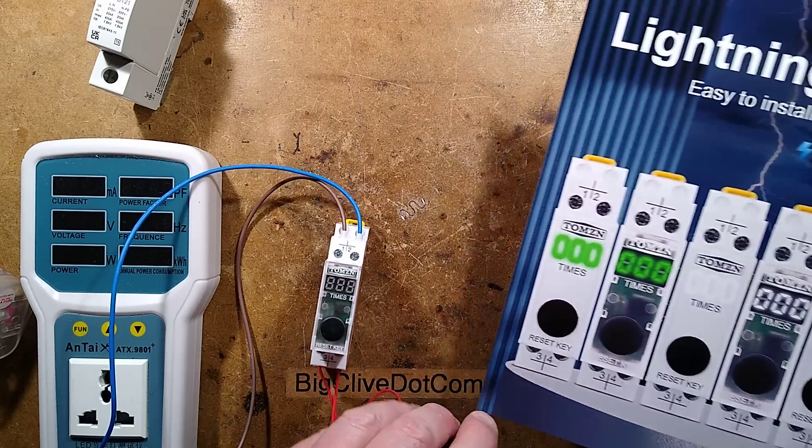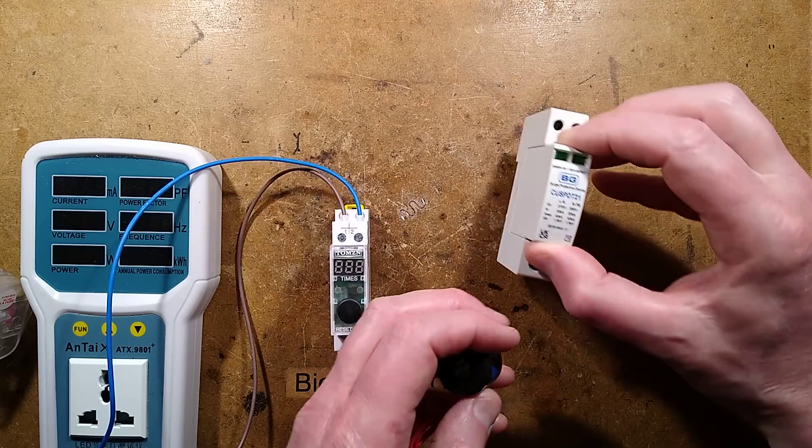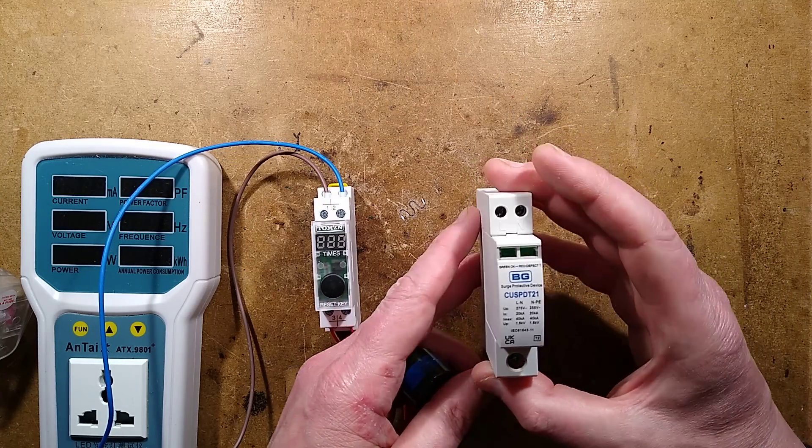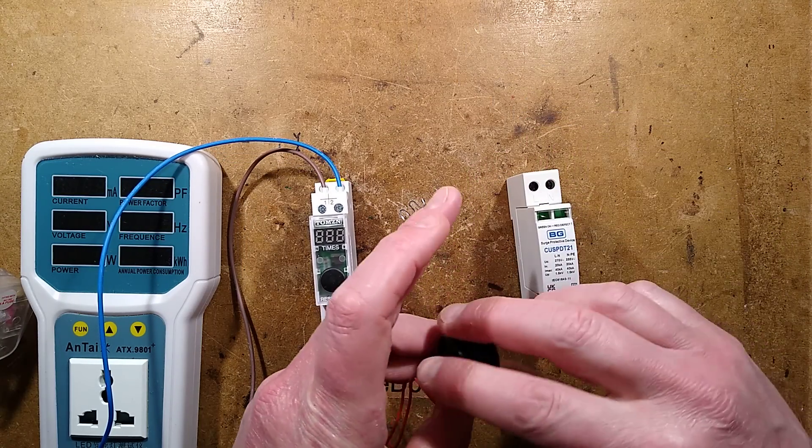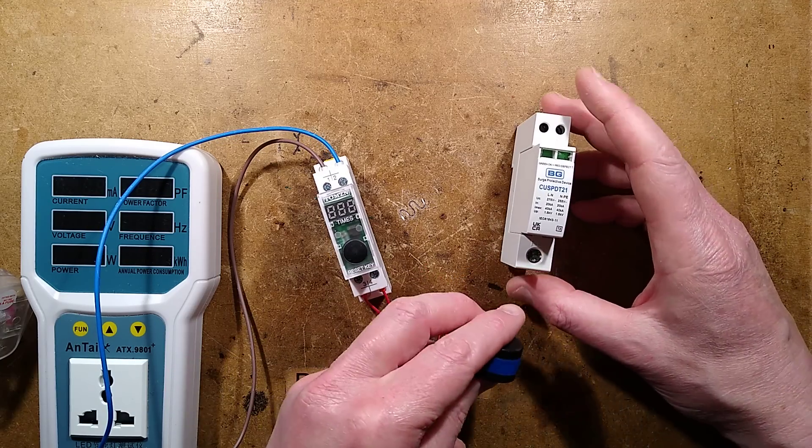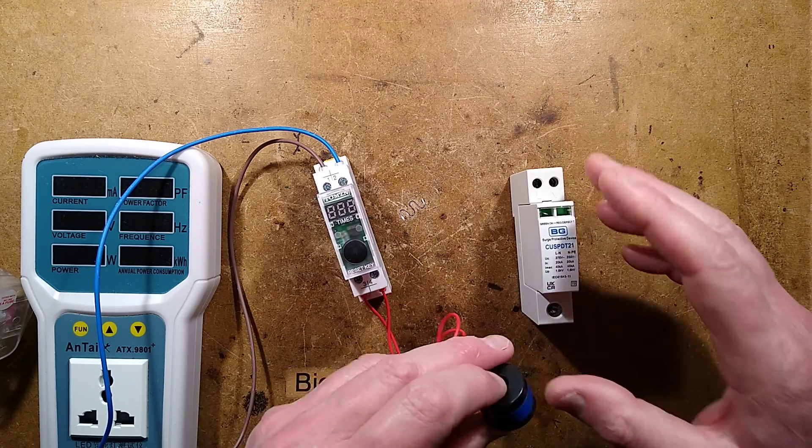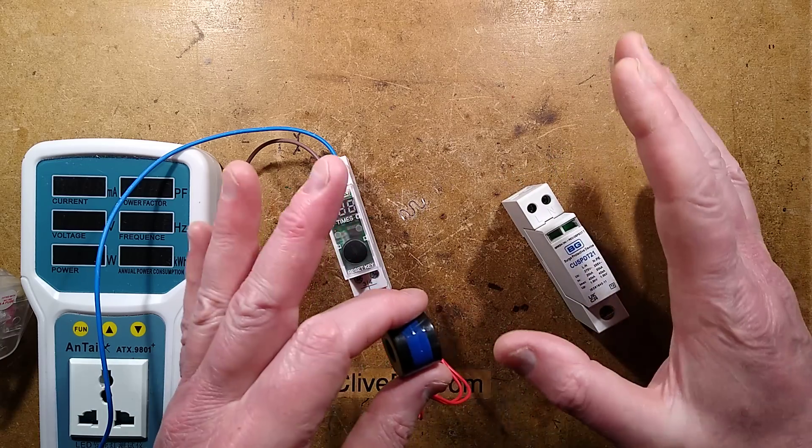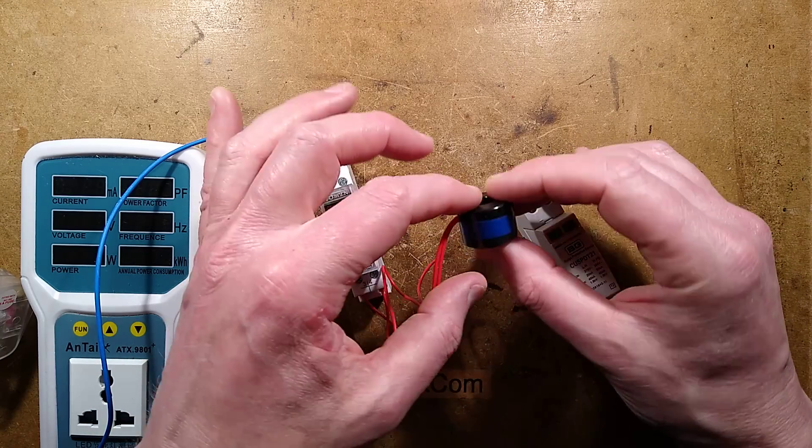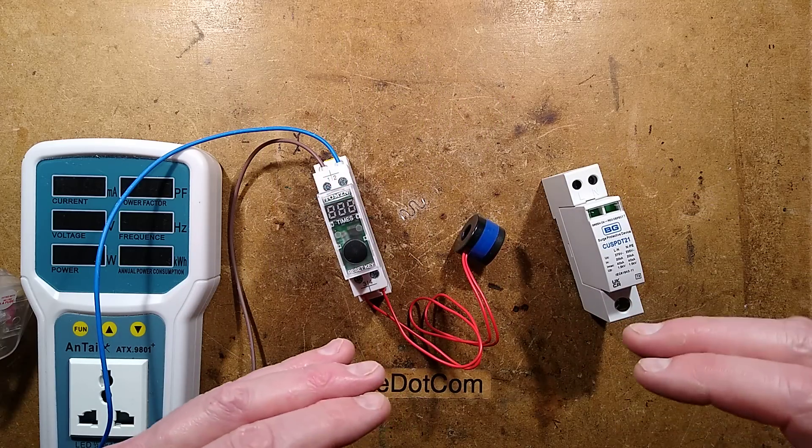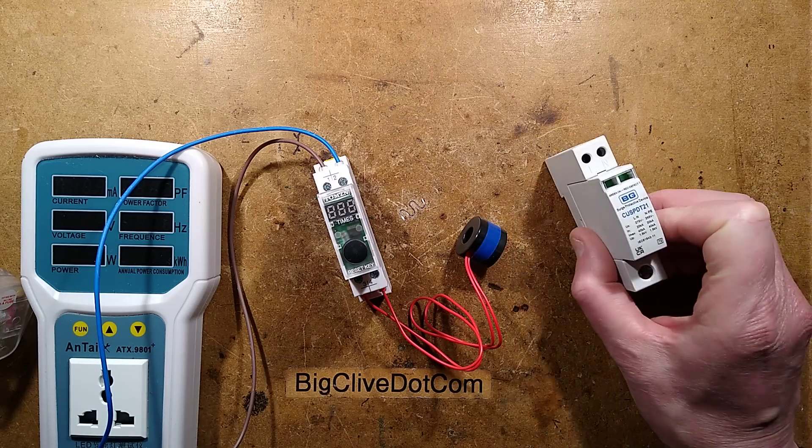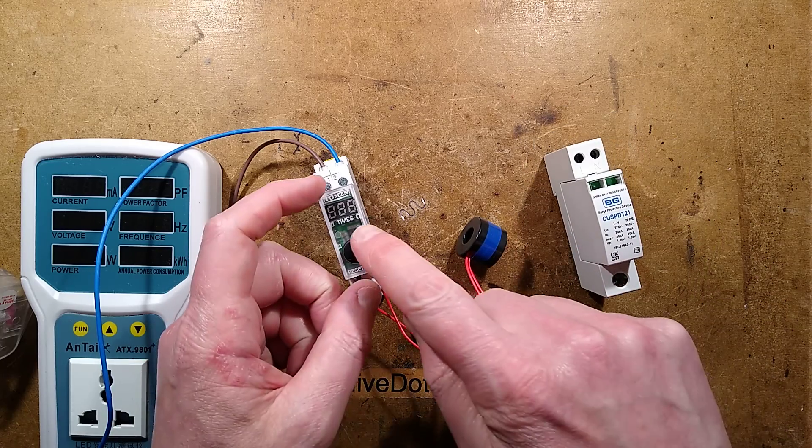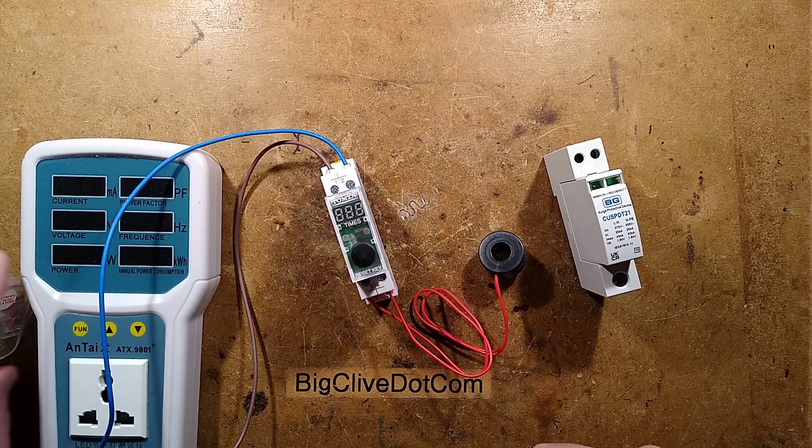This device basically gets used in conjunction with a SPD or surge protective device like this one. You put this around the live conductor or potentially, I suppose if it's going to earth, you could put it around the earth conductor. The instructions are vague, but wherever there's likely to be a high current pulse, that wire goes through the sense transformer and then through the unit. In the event of there being a huge power anomaly, this device kicks in and it shunts a spike. It will theoretically increment the display by one.